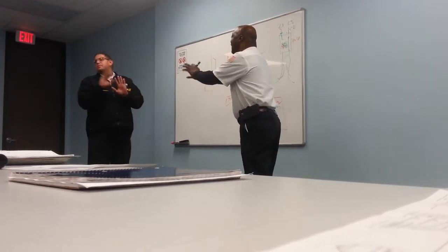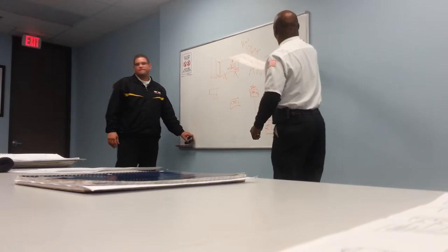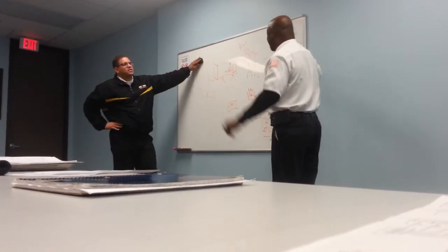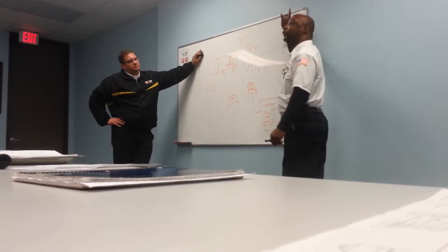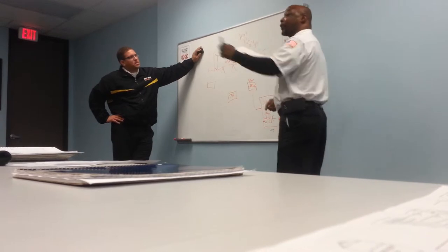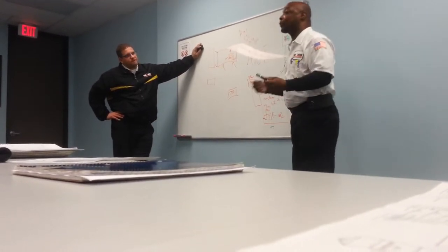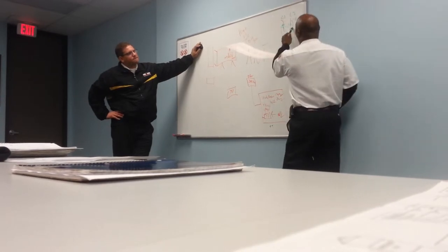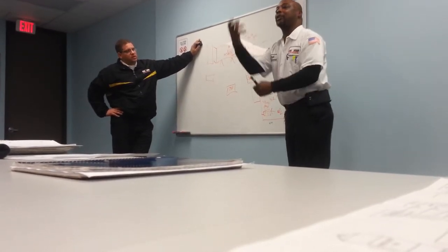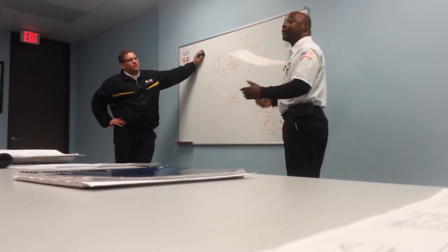The reason why I'm saying, let me say this. Guys, a single-pole contactor is going to send juice and it's going to go through that compressor and come back on this side. So if you take your meter and check 120 to ground, 120 to ground, you're going to get 120 on both sides. You've got to go across here. You've got to see the 240 on your meter. If you see 120 on your meter, you do not have 240.